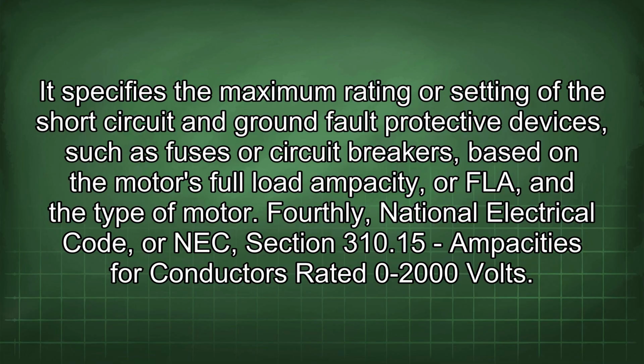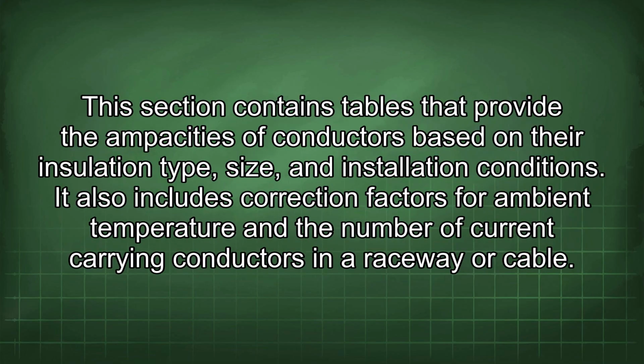Fourthly, NEC Section 310.15 Ampacities for conductors rated 0-2000 volts. This section contains tables that provide the ampacities of conductors based on their insulation type, size, and installation conditions. It also includes correction factors for ambient temperature and the number of current-carrying conductors in a raceway or cable.